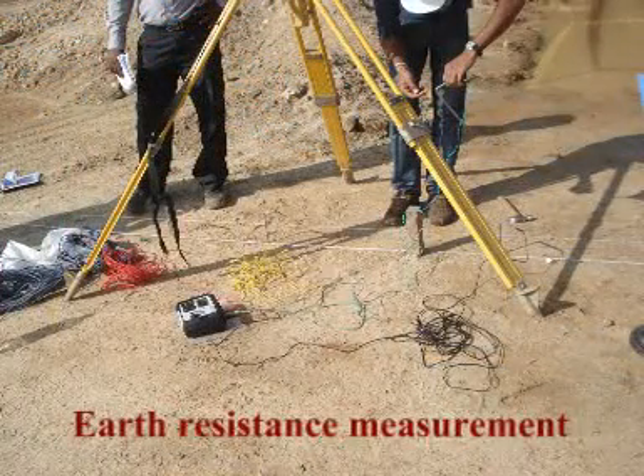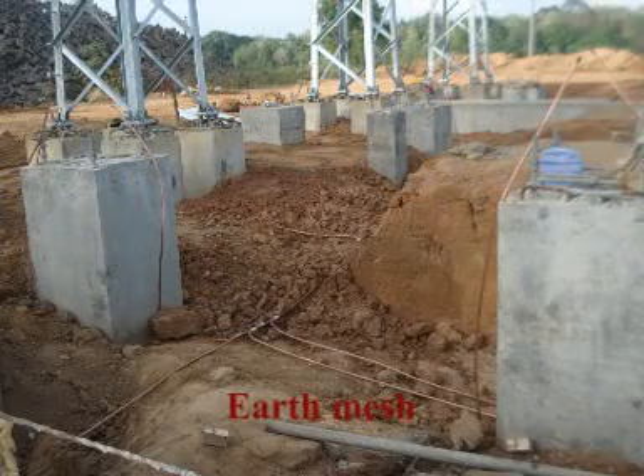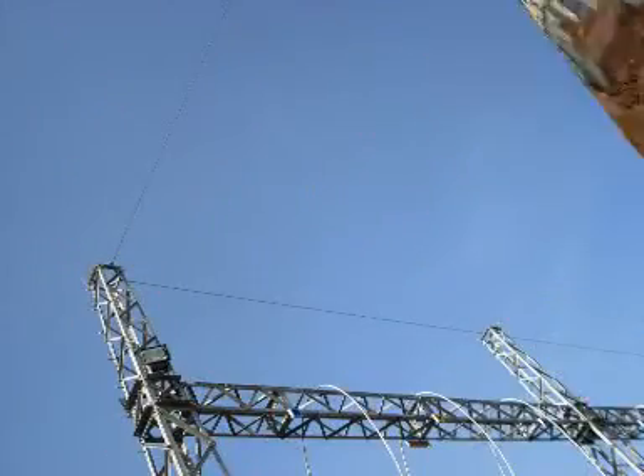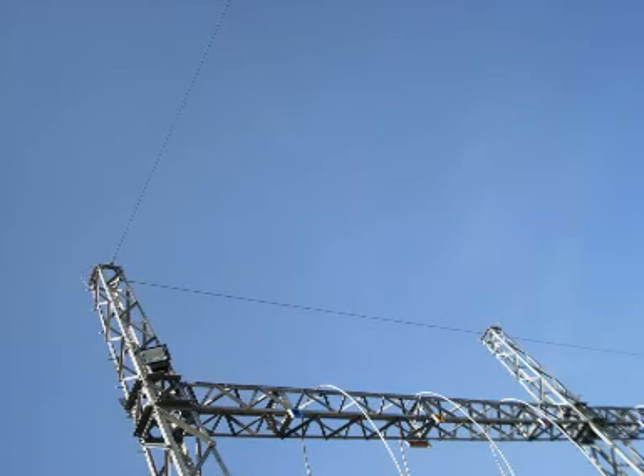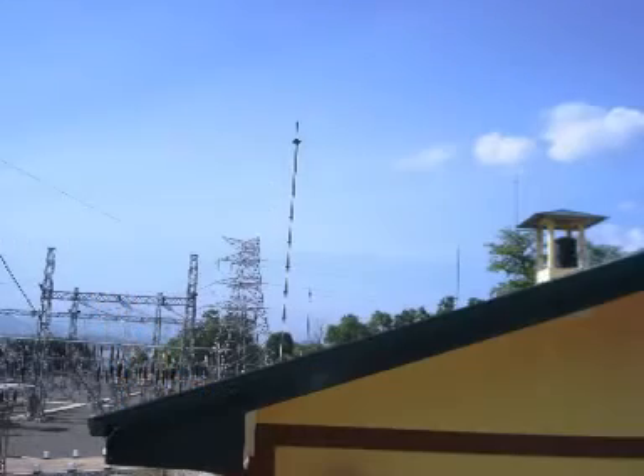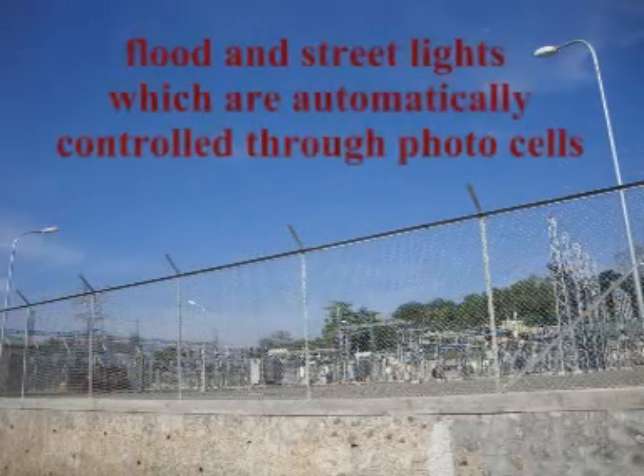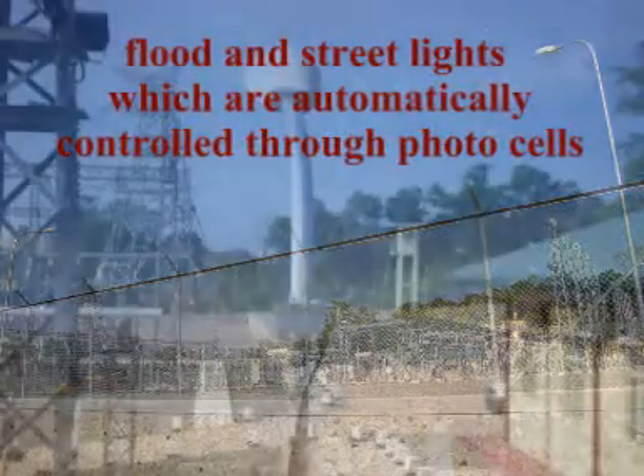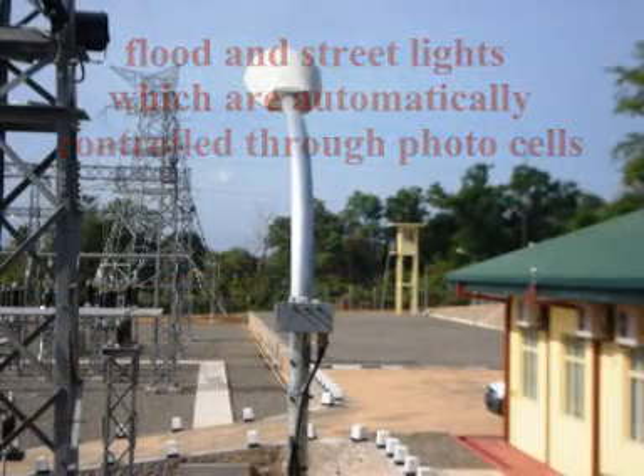All equipment and steel structures are properly earthed through the underground earth mesh provided. Also, overhead lightning shield wires are provided to protect outdoor equipment from external lightning strikes. Switchyard premises are lit by flood and street lights, which are automatically controlled through photocells.